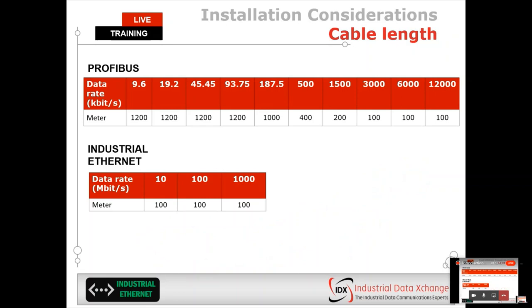So completely separate segments altogether, which means that for each of those segments, or between any two devices, the maximum amount of cable I can have is 100 meters. If you need to go a little bit longer, you have two options.